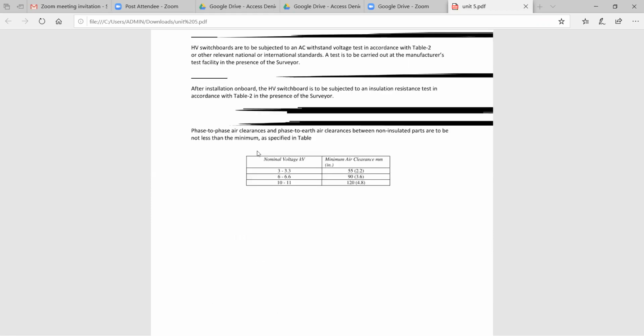These are the constraints considered for the minimum clearance with respect to the nominal voltage level. For 3 to 3.3 kV, we have a clearance of 55 mm, or 2.2 inches. Second, for 6 to 6.6 kV, 90 mm, which is 3.6 inches in brackets. For 10 to 11 kV, it is 120 mm. So these are the different clearance values which can be used on ships.